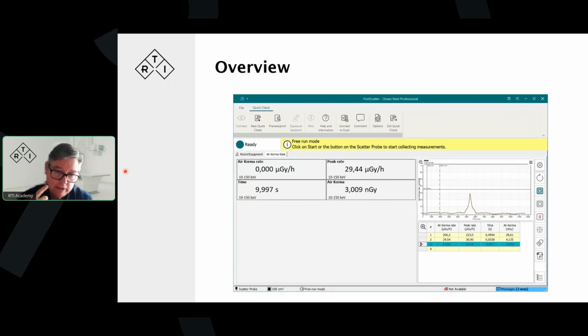That's a help to you if you're doing a long exposure and moving it slowly along a door jamb. When you stop, you get the waveform, and you can see after how many seconds you actually get the peak, like this one here. It's after about 5.5 seconds that I get the peak.